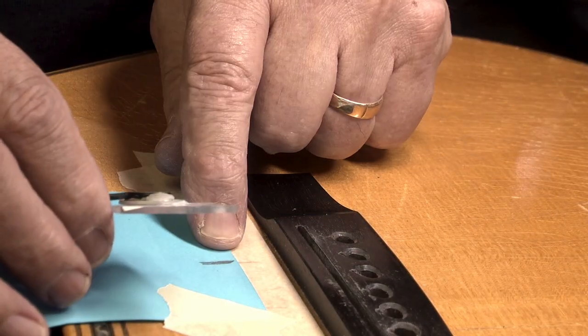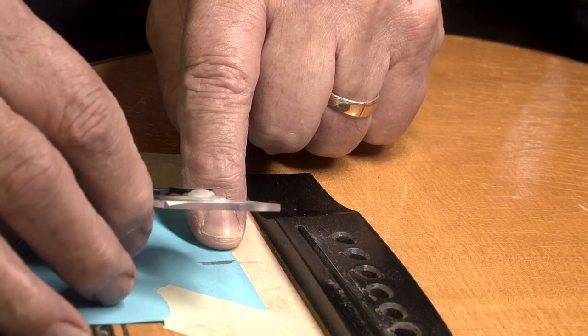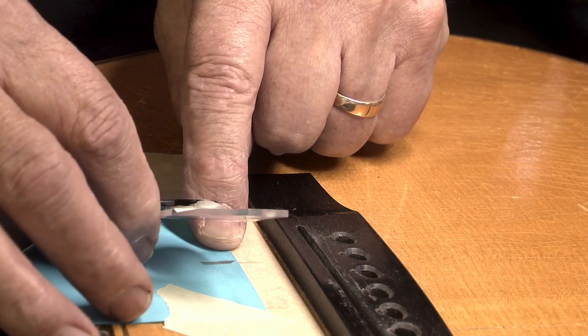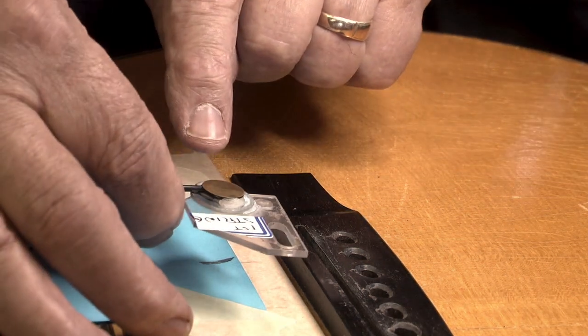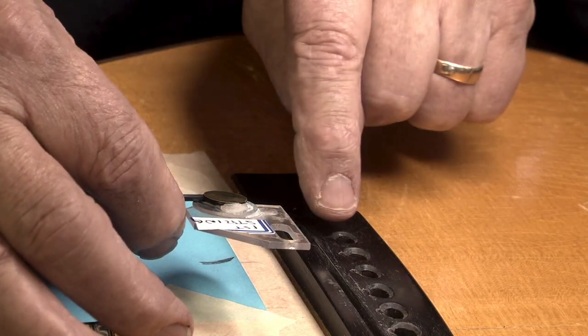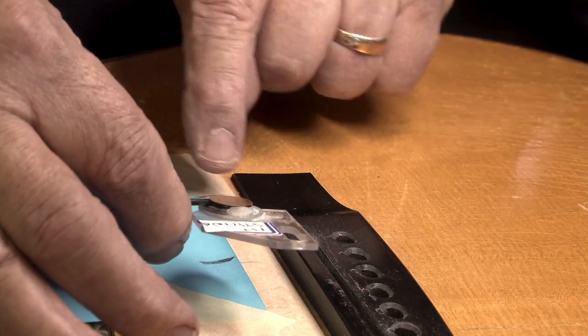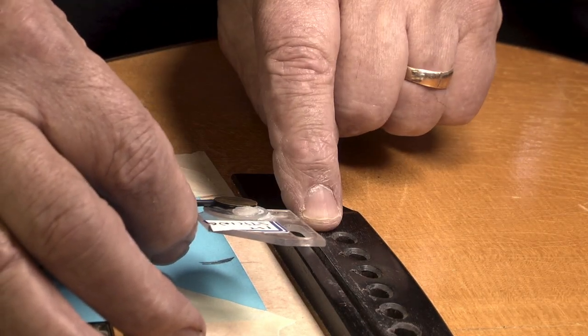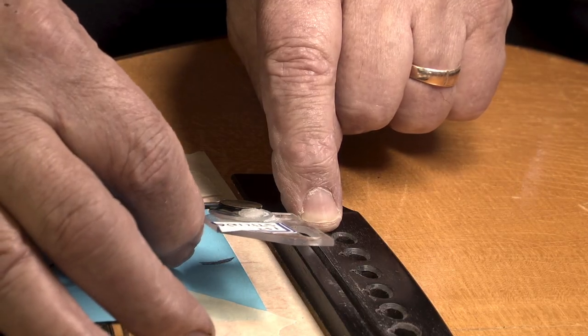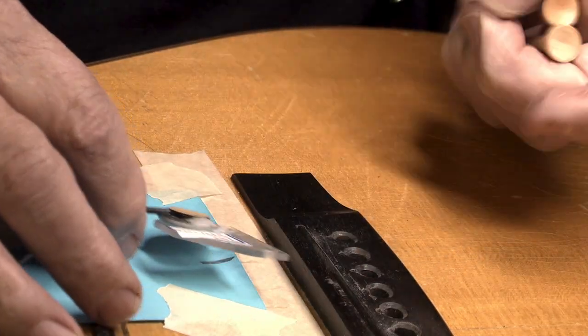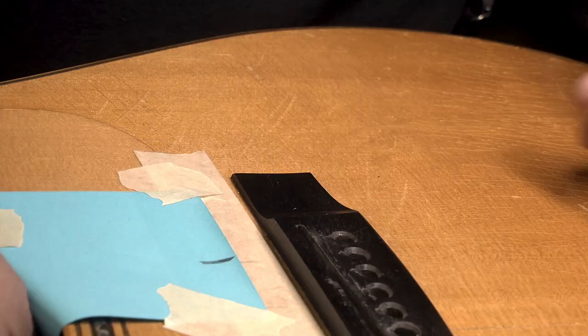For anyone new to this type of system, the first string is the one exception to the rule. Instead of attaching this transducer between the first and second string, you don't. You line it up dead center with the first string. This is the only transducer you do that with.